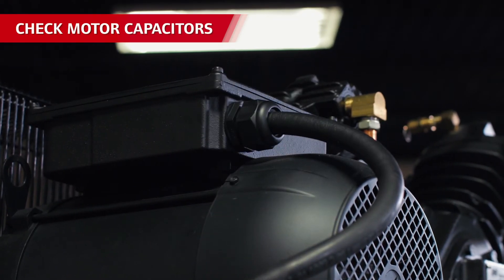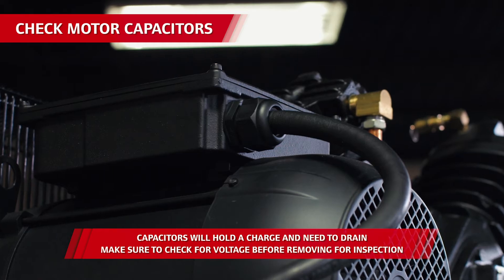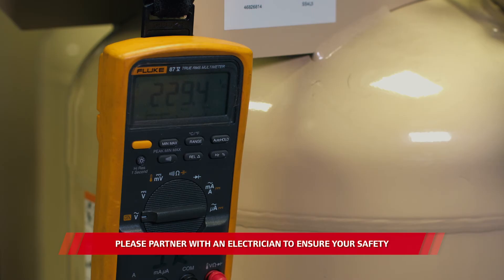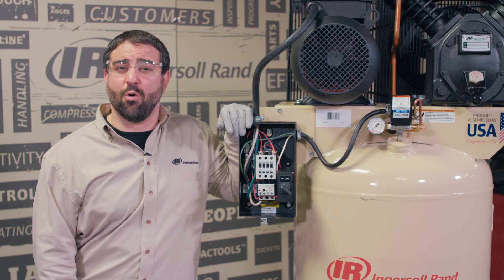Take a look at the motor capacitors. Just looking at them will show you if they're leaking, cracking, or swelling. The motor capacitors can also be tested — an electrical professional can perform a visual inspection for swelling, cracking, or leaking, and can also check the capacitance of the parts using the digital multimeter. An electrical professional can inspect and test the motor, or you can replace it.